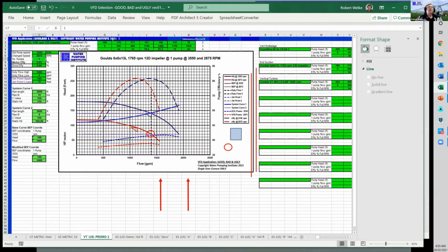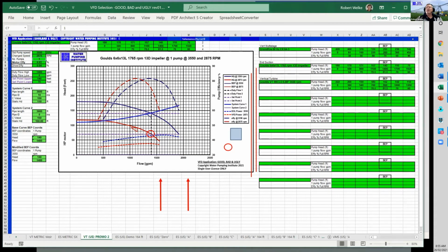You can see the coordinates of the pump curve at the top, and over here on the right, there are a range of other pumps which we can copy and paste across to this set of coordinates here. But of course, if we want a pump that's slightly different, instead of going looking for a pump in a catalog and copying the coordinates into here, we can change the shape of this pump curve. Now have a look at this.